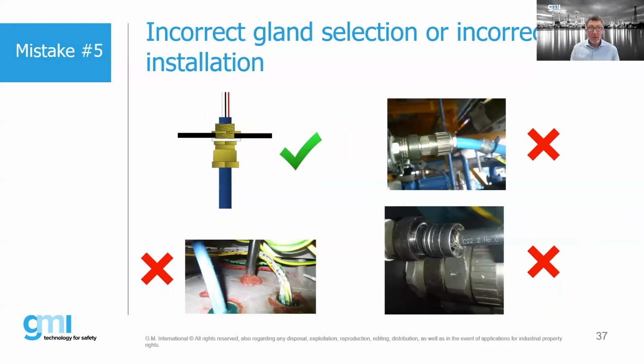Okay. Let's move forward. Number 5, incorrect gland selection or incorrect installation. So this is not necessarily just an IS issue, but one of the biggest issues that we see as an inspector of EX installations, regardless if it's EXD, EXE, EXI, whatever, is not installing the gland correctly. So that is one of the biggest issues. What we want to make sure is that when the glands are being installed, they're installed as per the manufacturer's recommendations. They are installed in accordance to the wiring regulations of whatever country you're following.